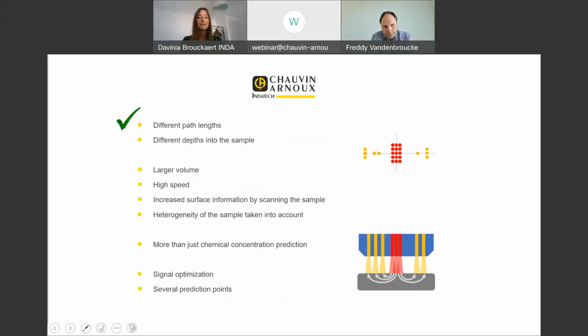Due to its patented design, the SRS probe offers the advantage of being able to measure different path lengths and different depths into the sample, which allows to measure larger volumes in comparison to classical NIR spectroscopy. As I've stated before, this simplified hyperspectral imaging system also allows for high-speed acquisitions, and by moving the sample underneath the probe, for instance, or in front of the probe in case of inline acquisitions, multiple acquisitions can be performed on one and the same sample, and this further increases the surface information that we can obtain, and to a certain extent also allows to take some heterogeneity or potential heterogeneity of the sample into account.